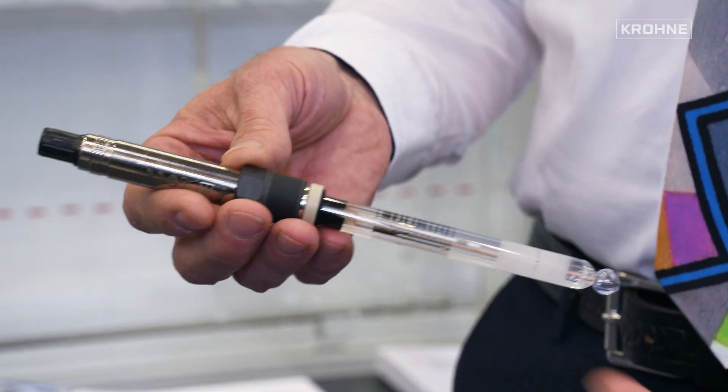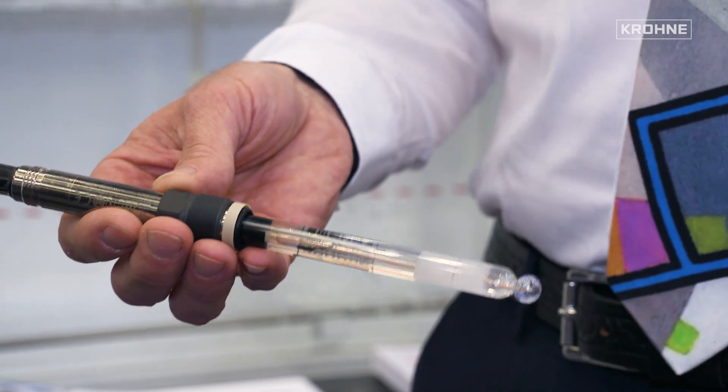SmartPAT means that we have an analog sensor like a pH probe shown here, where we have integrated the complete electronics needed to work with a pH probe into the connector of the electrode. Normally, when a customer is using pH or conductivity sensors, he has a sensor, a cable, and a transmitter — a very expensive setup. A lot of customers do not want a big transmitter in the application anymore; it's taking too much room. So we've decided, especially for skid builders, that we are shrinking the electronics to a size like that.